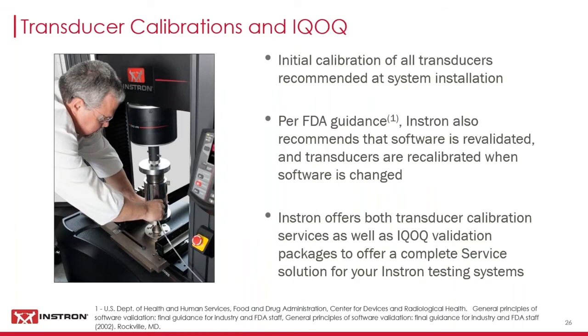Transducer calibrations also play a role in IQOQ validation of the system. To ensure that your testing instrument is providing accurate data, Instron always recommends initial calibration of all transducers upon installation of the equipment on site, and recalibration if certain components are repaired or replaced. Since most materials testing instruments now utilize software, a common question from our customers is whether they should perform a recalibration when software is updated or upgraded.